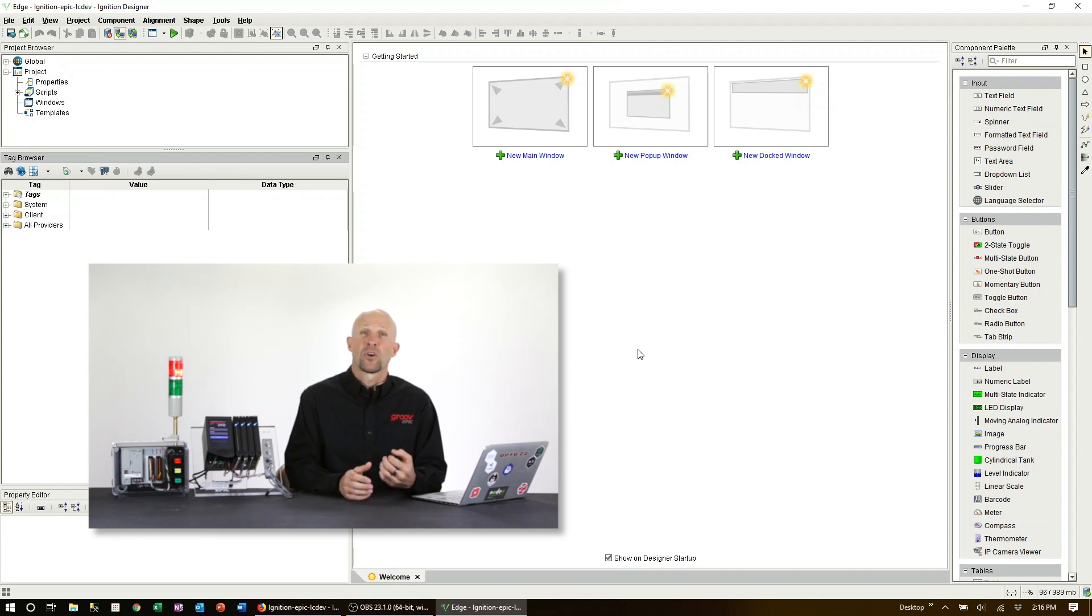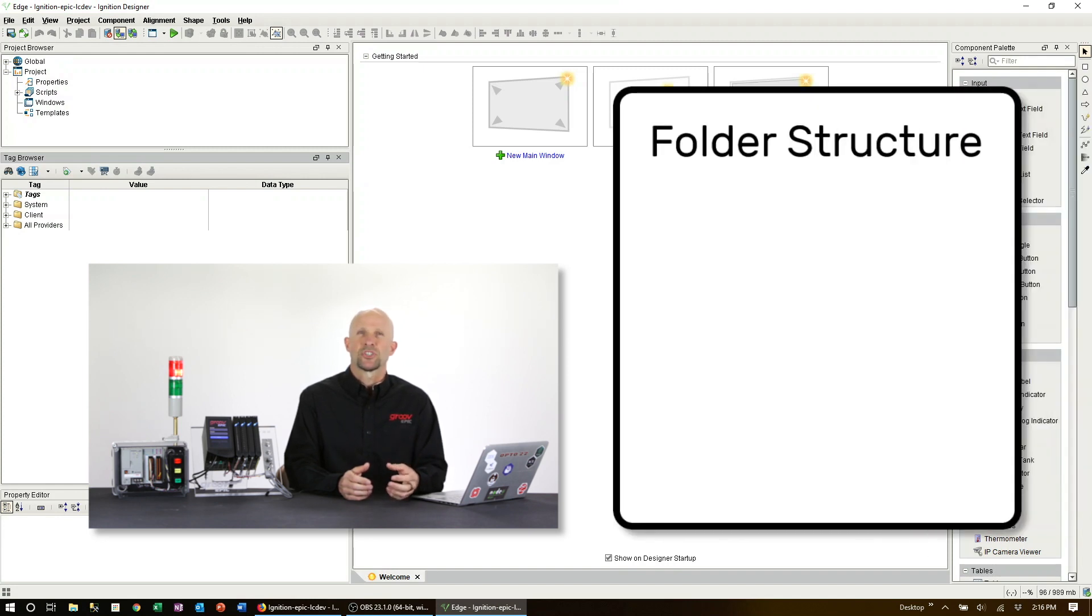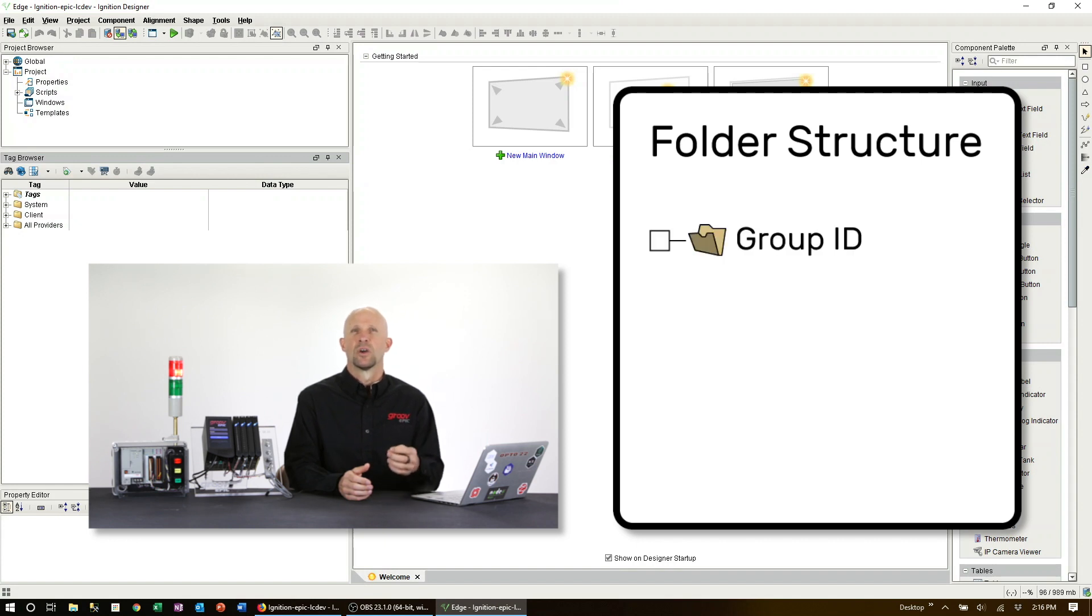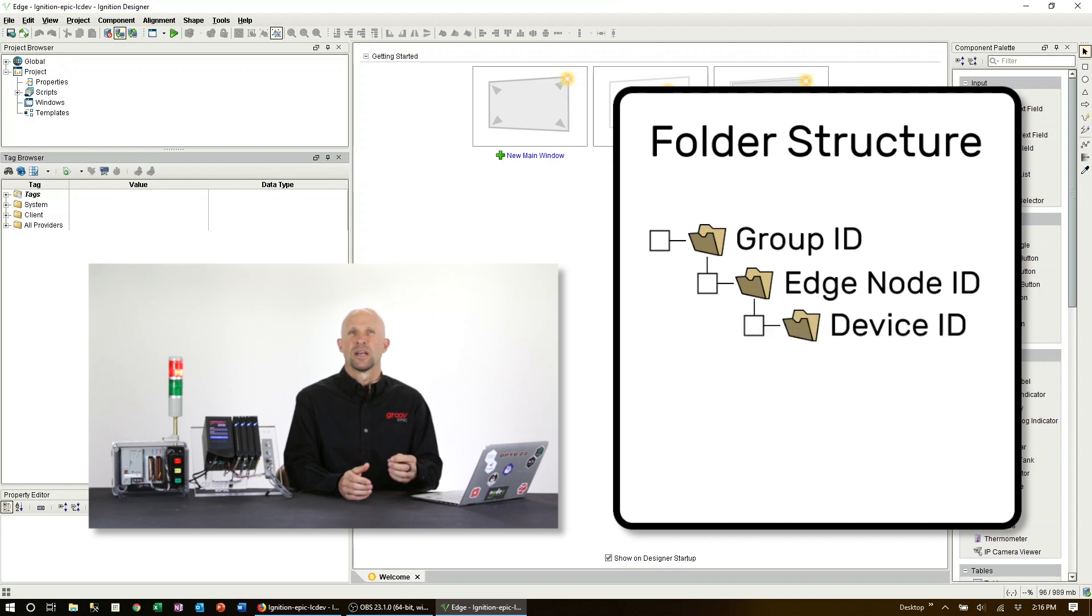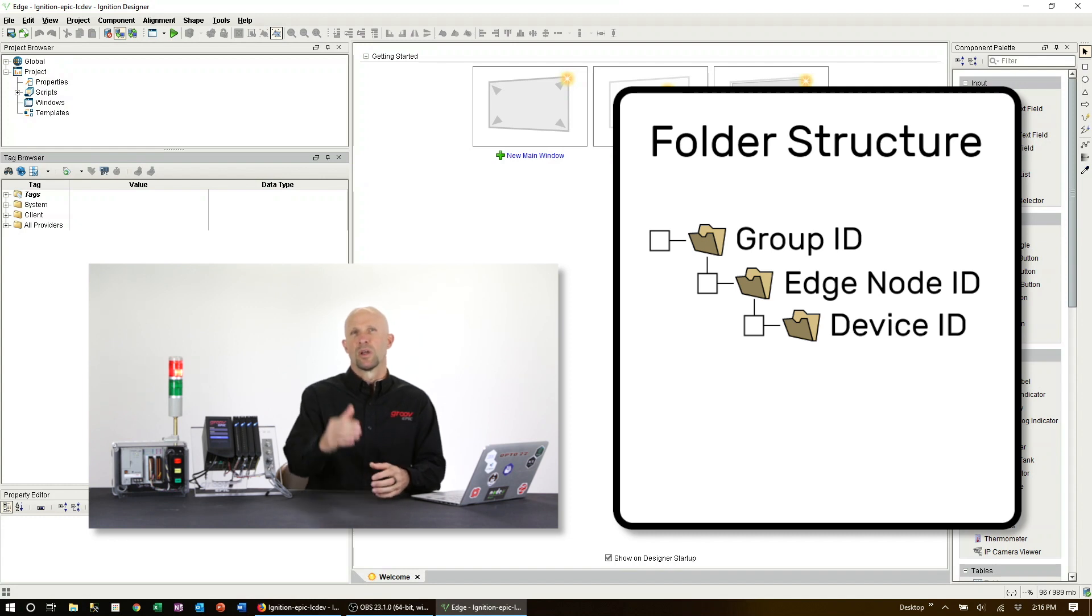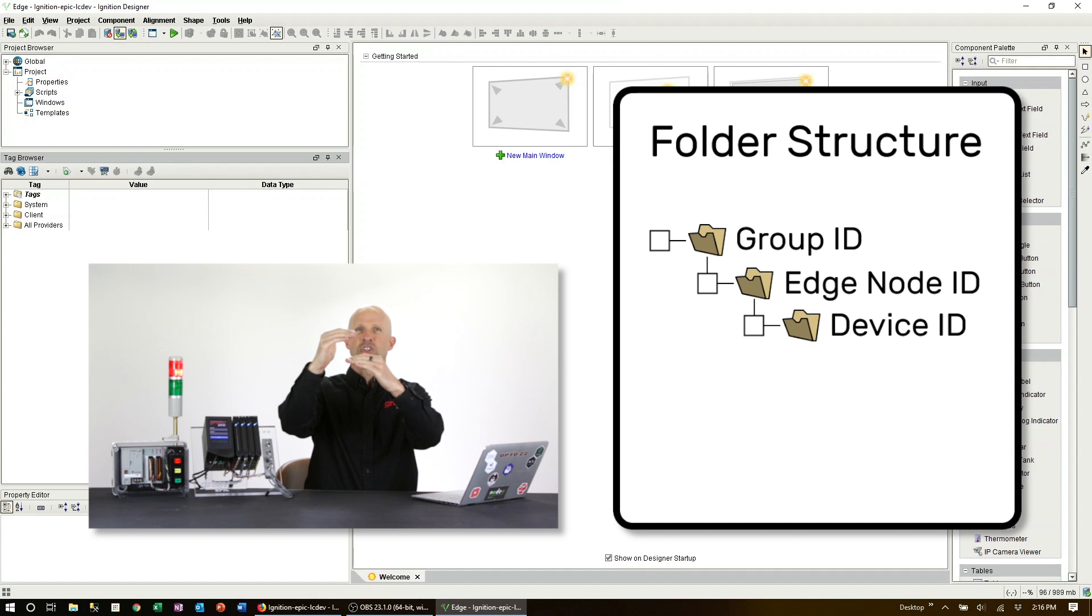Let's start by creating the required folder structure that MQTT Sparkplug uses. That folder structure consists of three nested folders: Group ID, Edge Node ID, and Device ID. You can name them anything you like but the structure is really important. The top folder is Group ID then the Edge Node ID under that and lastly the Device ID.